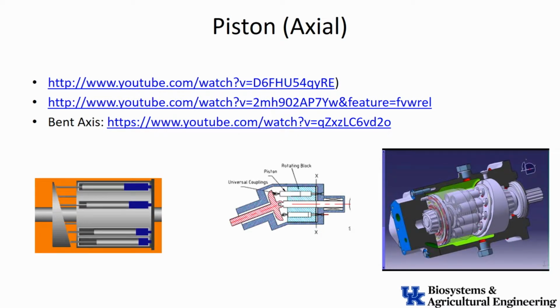And as that barrel rotates, we have this plate, this slanted plate on the left-hand side. We call that plate a swash plate. And the swash plate actually is going to be connected in some way. We can do it a lot of different ways, but it's connected to the pistons. The pistons are in that barrel.